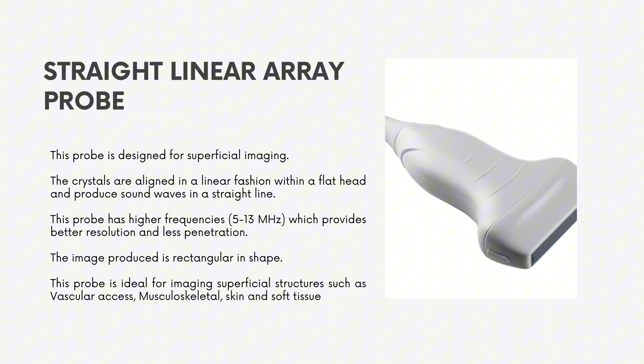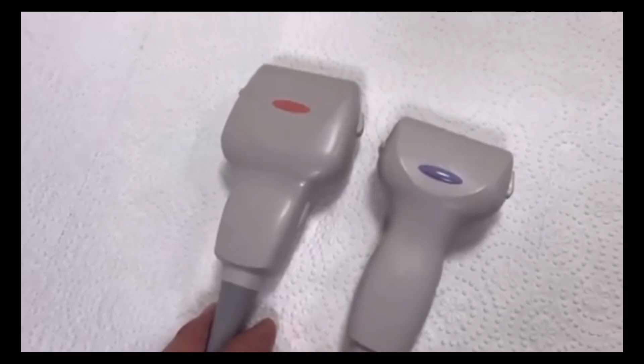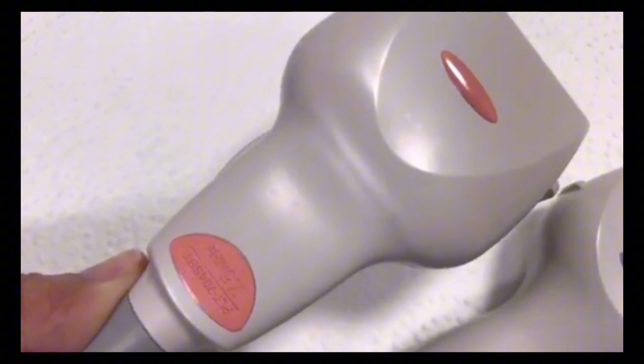Straight linear array probe. This probe is designed for superficial imaging. The crystals are aligned in a linear fashion with a flat head and produce sound waves in a straight line. This probe has a higher frequency, which provides better resolution but less penetration. The image produced is rectangular in shape. This probe is ideal for imaging superficial structures such as vascular, musculoskeletal, skin, and soft tissue.